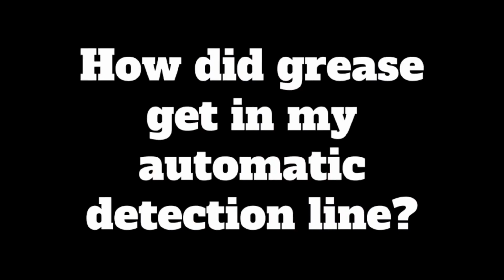How did grease get in my automatic detection line? When you're cooking, it produces grease vapors. These vapors can attach themselves to that line, locking it up over a period of time. It's not an uncommon thing. We check to ensure that your cable is moving freely so that your system will set off automatically if needed.